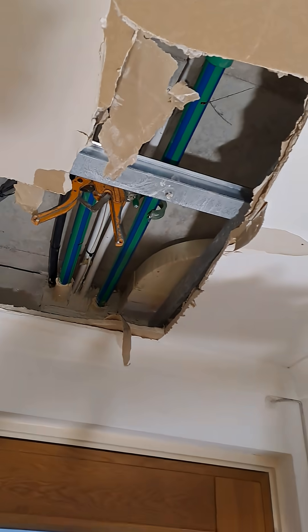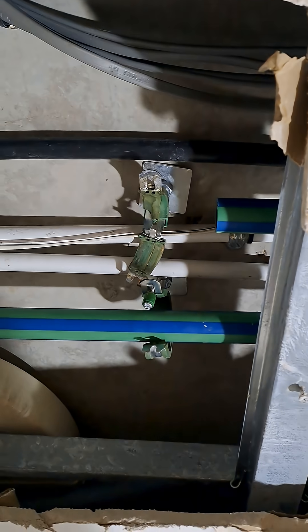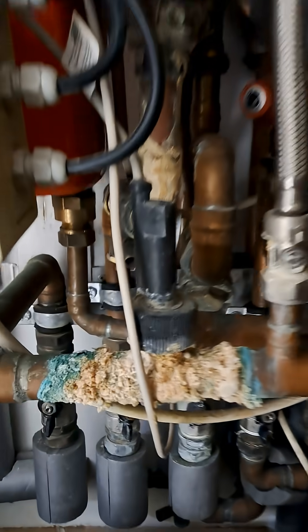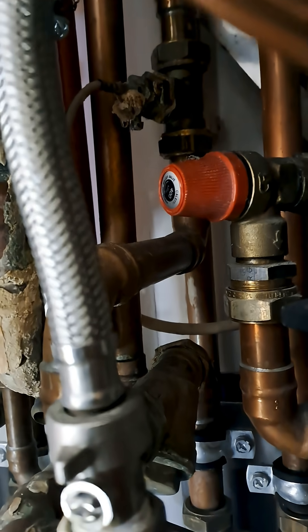It was a nightmare to find a drain-off washer afterwards. I was trying to mentally visualize everything that was going to happen before starting, so I had everything I needed. I got the thermal iron up to temperature, cut the pipes, and pushed my joints on. I didn't order extra copper fittings, so there's the leak on the HIU.